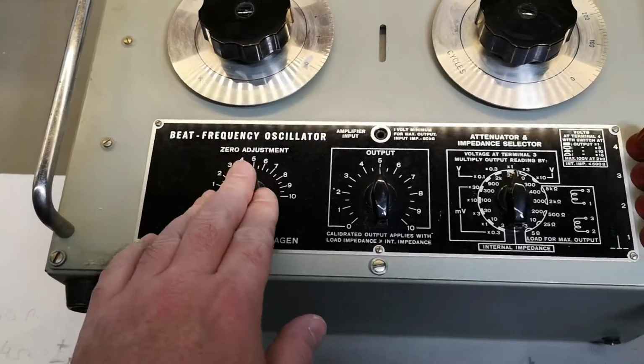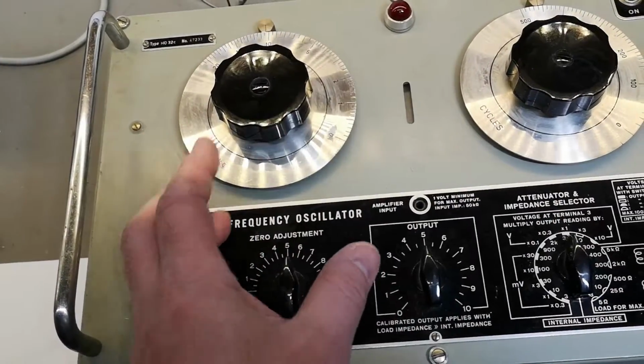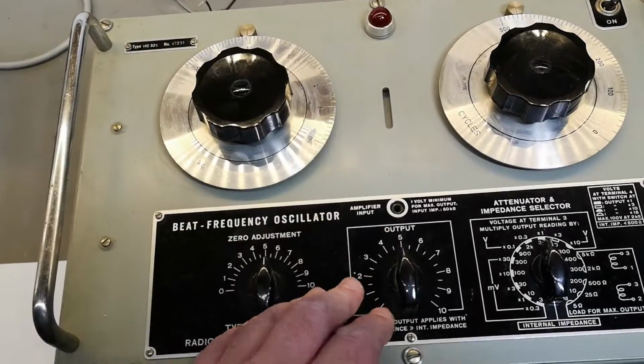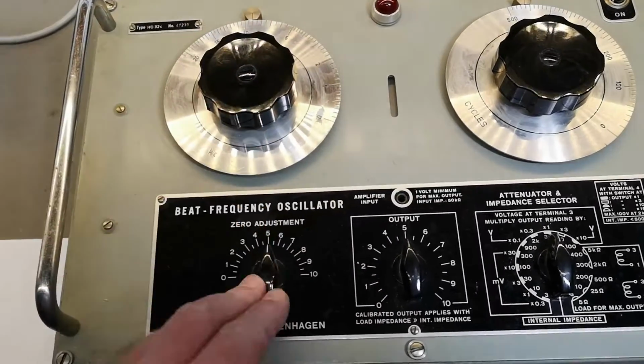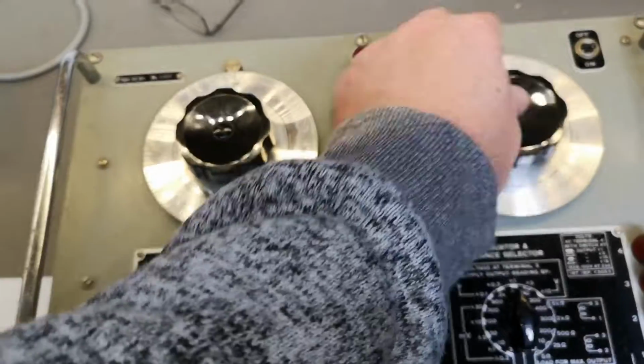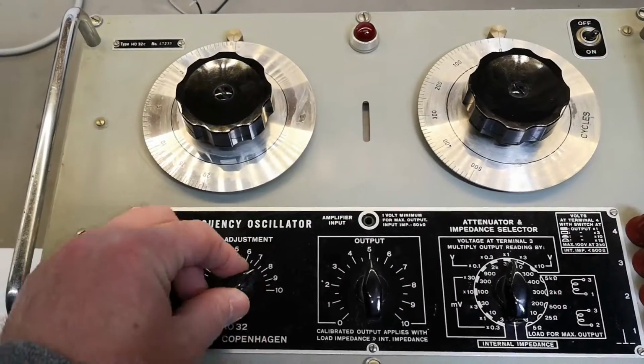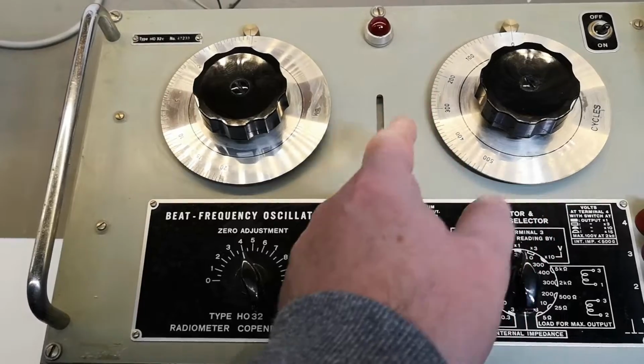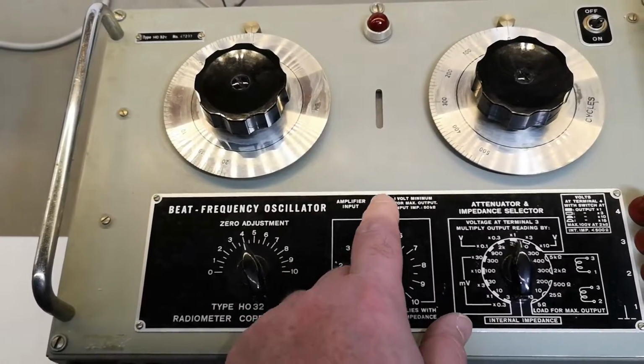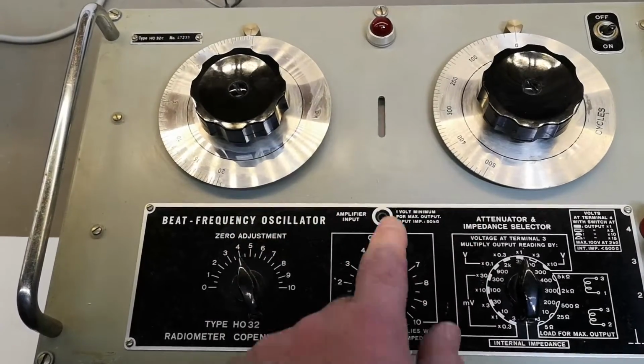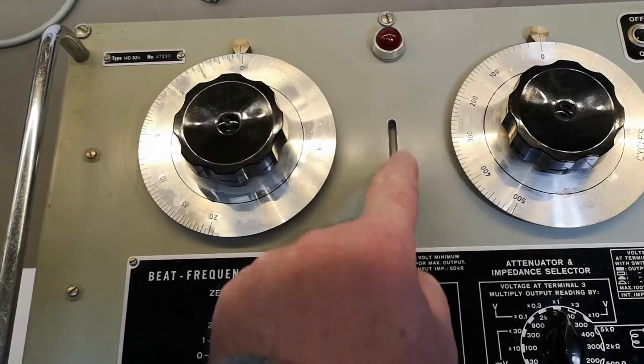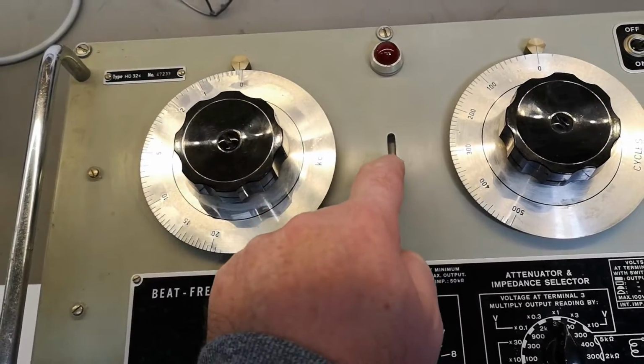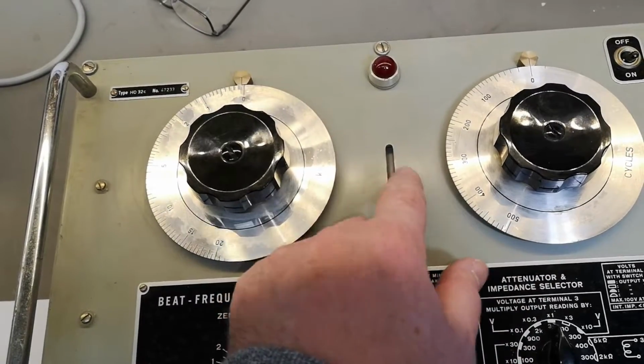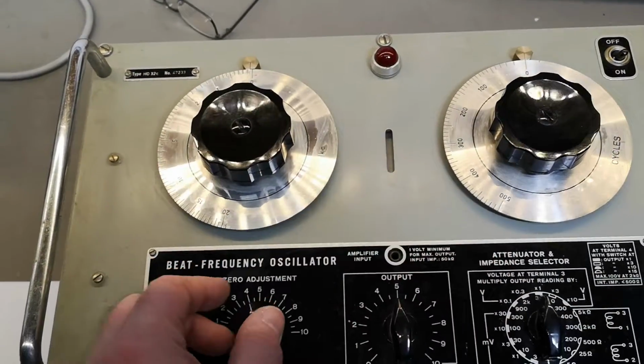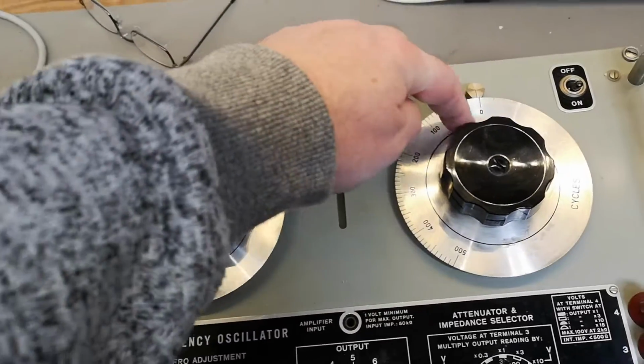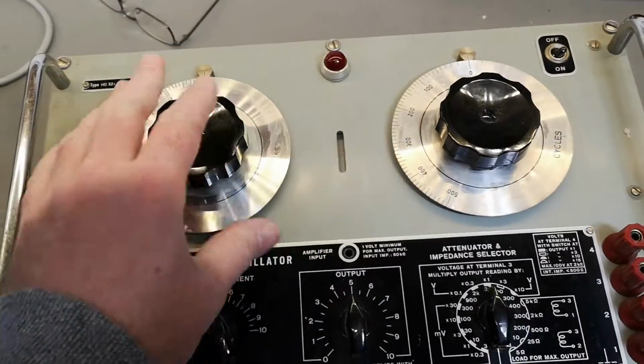About zeroing adjustment: because the two oscillators beat together to create the output, one of them you can fine tune. So you set this for zero and that for zero, then fine tune until you get zero output. The output frequency drives this meter, so you'll see a pulsing, a low frequency pulsing, because the difference actually does go to zero hertz. Then you know the two indicators here are correct.